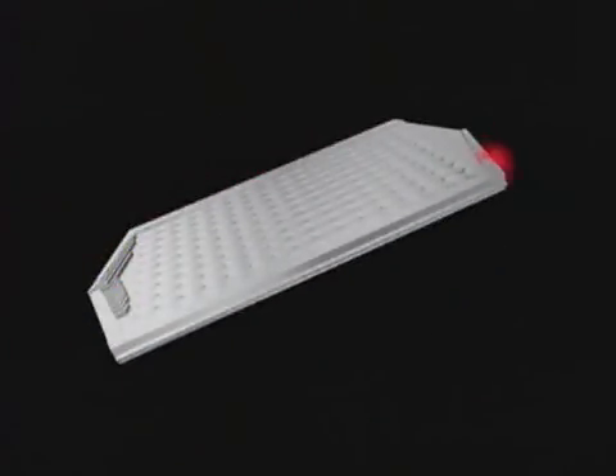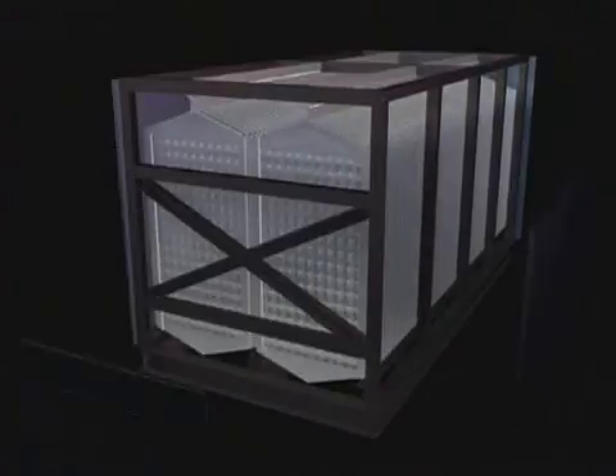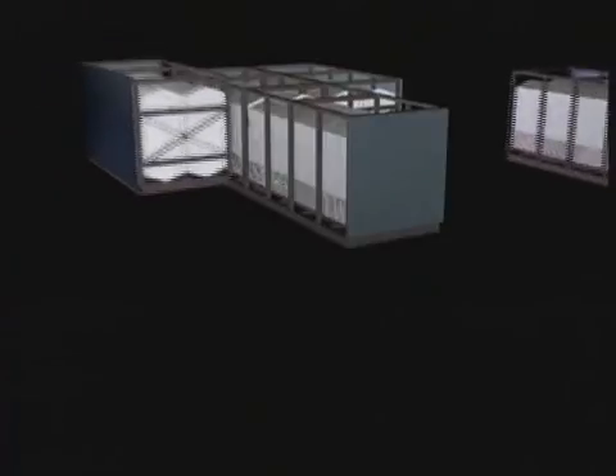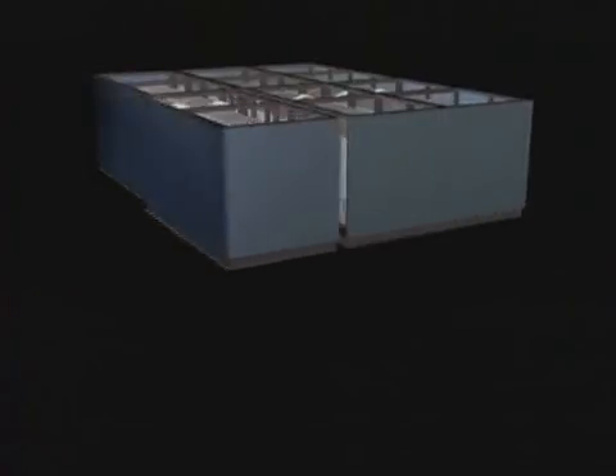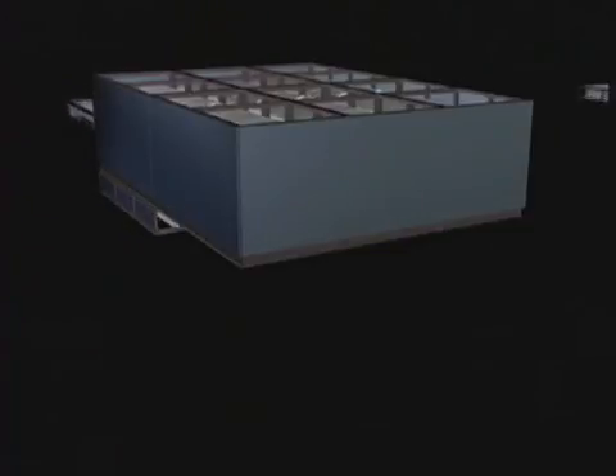Plate pairs are stacked one on top of the other and are welded together to form plate packs. The easily handled plate packs are then assembled into modules. The module size can be varied to suit individual site requirements and transportation restrictions. As the exchangers become larger, it is simply a matter of adding more modules. This eliminates the problems associated with increased duties and upscaling of equipment.